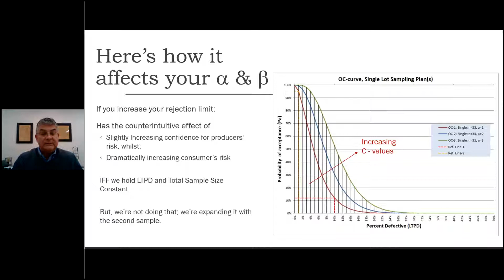Let's click in and we'll see if we accept again a 10% LTPD, lot tolerance percent defective, that's our patient risk. That ends up giving us a probability of about 12%. So this is for a lot size of 500, a sample size of 35, and we set that LTPD at about 10%. That may be high for some of you out there. You may say, oh, I would never do that for my patient risk. But it's just a starting point to give you an idea of how we can balance this.